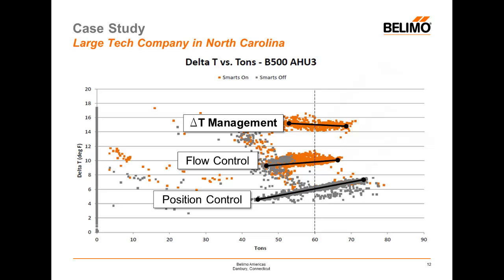In position control, in order to serve 60 tons of cooling at 6 degrees F, 240 gallons a minute were required. In flow control, to serve the same 60 tons near 10 degrees Fahrenheit required almost 100 gallons a minute less water than position control. And with Delta-T manager engaged, the same 60 tons only requires 96 gallons a minute. So the difference between a standard control valve and a valve with Delta-T management reduced flow from 240 gallons a minute down to 96 — that's 40% of the original flow rate to serve the same amount of load.